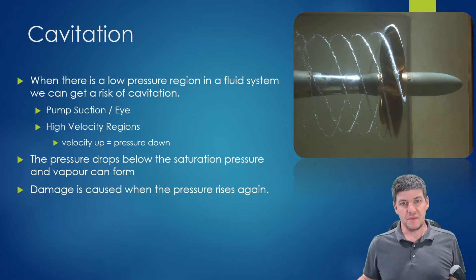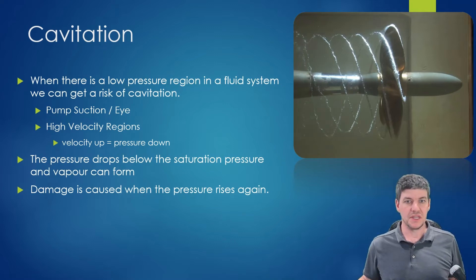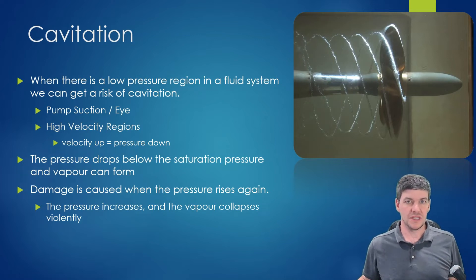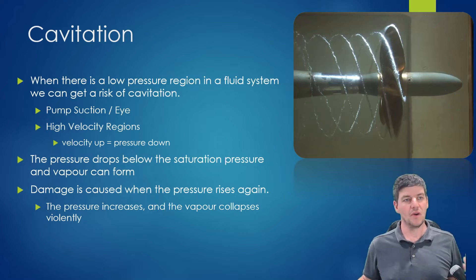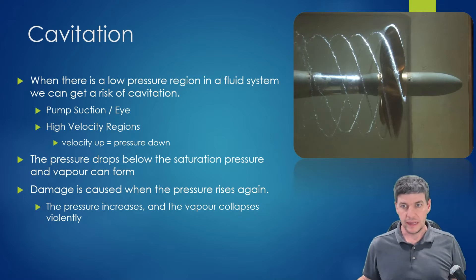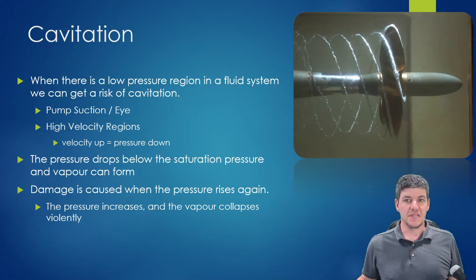A vapor bubble forms, and then when the pressure rises again, that bubble collapses. The surrounding fluid rushes in to fill that space and impacts against the surface. Over time, repeated impacts create damage — the pitting you typically see in impellers and other components — indicating that cavitation has occurred.